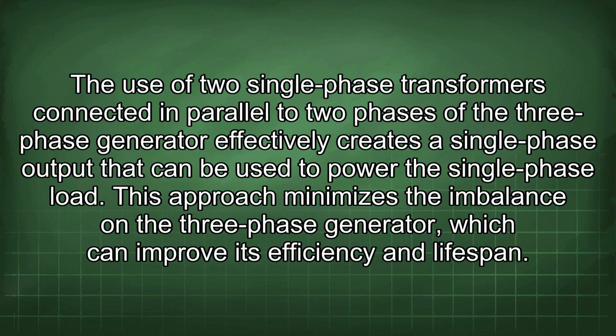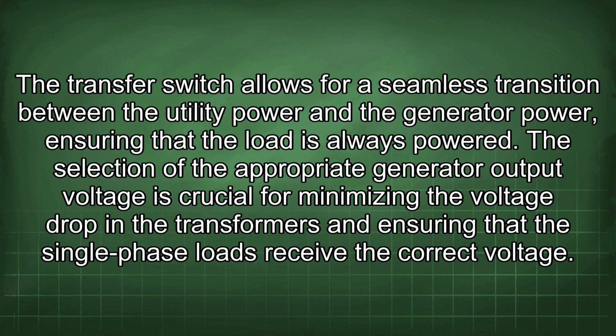This approach minimizes the imbalance on the three-phase generator, which can improve its efficiency and lifespan. The transfer switch allows for a seamless transition between the utility power and the generator power, ensuring that the load is always powered. The selection of the appropriate generator output voltage is crucial for minimizing the voltage drop in the transformers and ensuring that the single-phase loads receive the correct voltage.